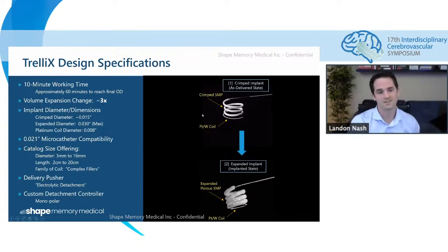The coil starts at about 15 thousandths of an inch crimped and then ultimately expands to 30 thousandths, and then the platinum backbone coil is 8 thousandths of an inch. And as I mentioned, we're indicated for an 021 microcatheter compatibility. Our current catalog size offerings are from 3 to 16 millimeters in diameter and 2 to 20 centimeters in length.